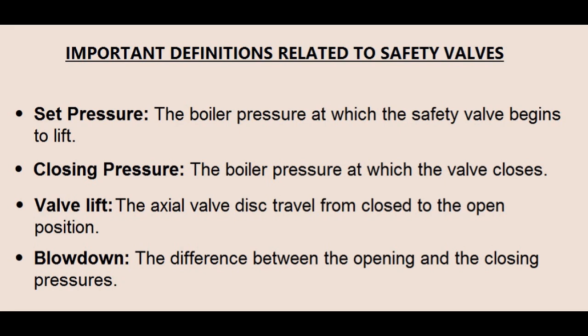There are some important terms related to safety valves. Set pressure: the boiler pressure at which the safety valve begins to lift. Closing pressure: the boiler pressure at which the valve closes. Valve lift: the axial valve disc travel from the closed to the open position. Blow down: the difference between the opening and the closing pressures.